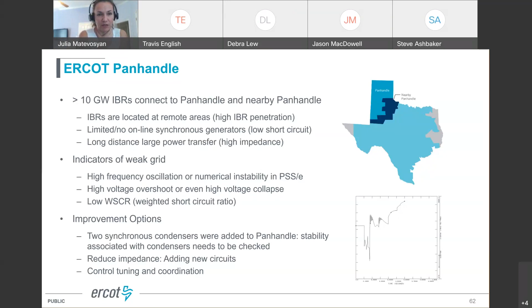So the previous slide was an overview of the problem, and now I'll drill into this a little bit deeper. The ability of a power system to operate in a stable manner and to recover from major disturbances is influenced by the electrical strength of the system at the point where the equipment is connected. Stronger systems are more tolerant to variations and perturbations occurring within a connected plant and recover more easily from major disturbances such as faults or sudden loss of equipment. But basically, what system strength really characterizes is how electrically far an interconnection point is from a strong voltage source.